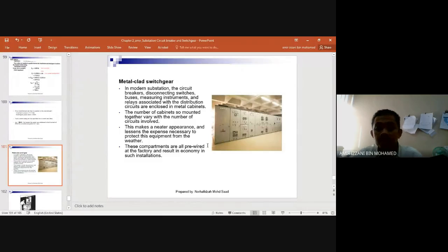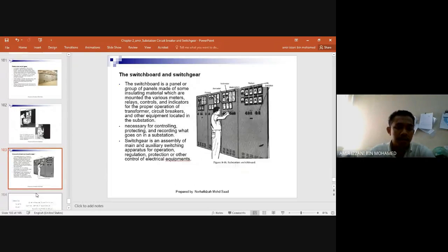This is what I showed you just now at the beginning of this class. This is very old switchgear. You can see the meter here is analog. So this is switchgear. It consists of a lot of things: circuit breaker, switch, disconnecting switch, bus, measuring instrument, and relays, associated devices, and it is enclosed in this metal cabinet.